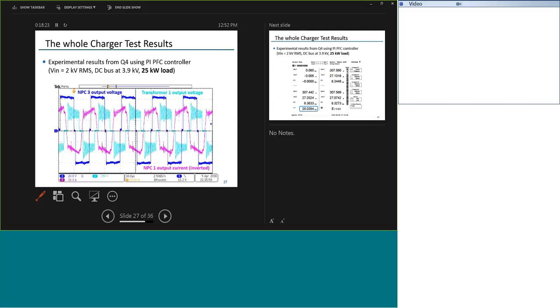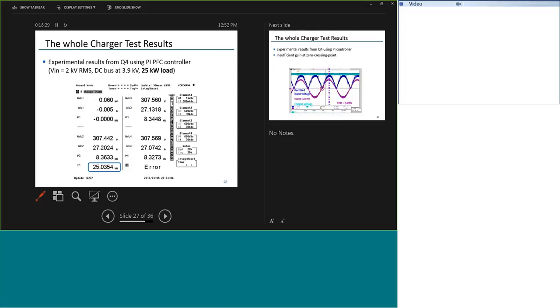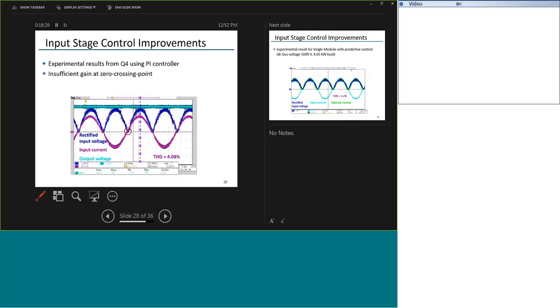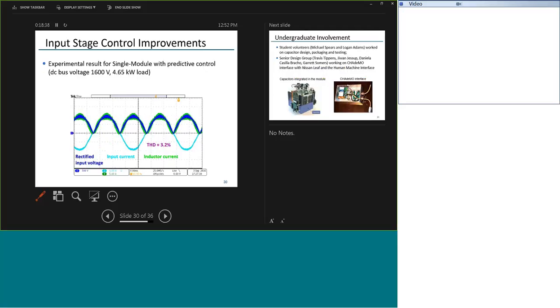Moving on, here are some additional experimental results showing the interleaving and showing the power output. Again, this slide shows the distortion around the zero crossing, and this shows the experimental results for a single module. With the predictive control, you can see the THD is reduced. When we combine the 3 modules and implement the interleaving, we believe it can be well below 2% THD, which will allow us to further reduce the switching frequency of the system.